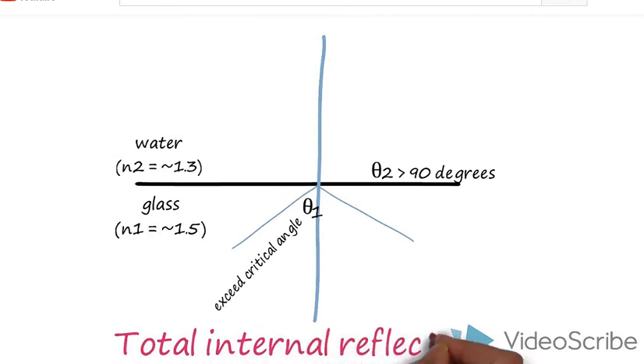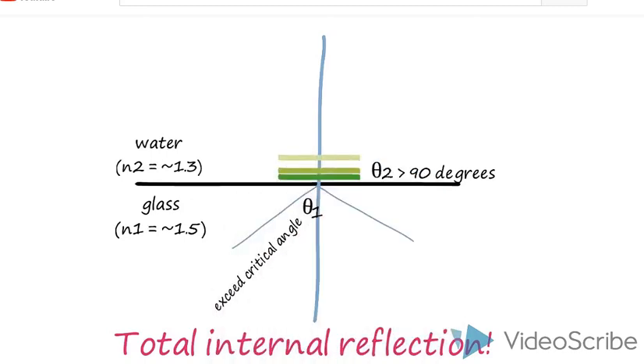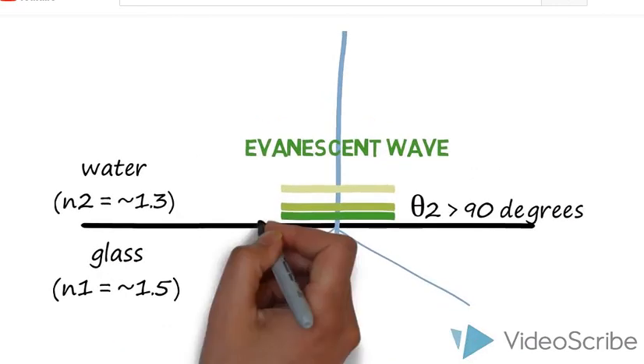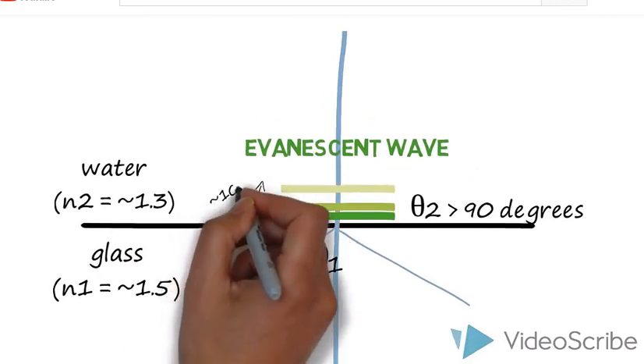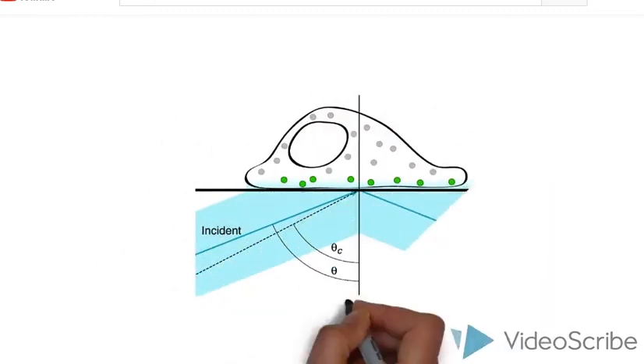If the light is totally reflected, then how do the fluorophores near the interface get excited on the other side? Well, it turns out that an evanescent wave is generated at the point of total internal reflection. This energy source decays exponentially from the interface and travels about 100 nm up into the second medium, which contains your sample.